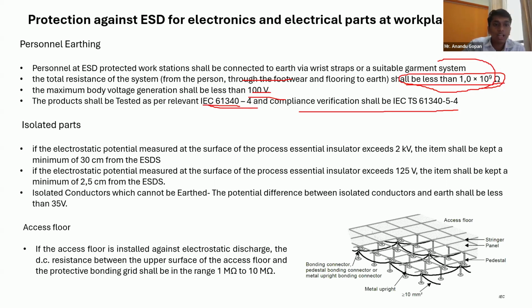If you have an isolated part, basically conductors or anything isolated that cannot be connected to your PE, functional earthing, or equipotential bonding point, and if the electrostatic potential at that region can exceed 2 kV, you should place them at least 30 centimeters away from equipment prone to electrostatic discharge. Better to keep it 30 centimeters away, and you don't need to be worried.